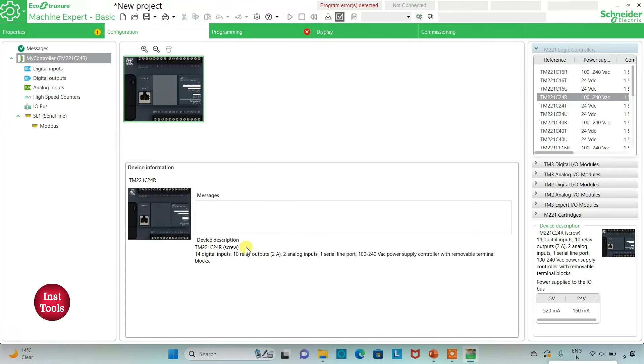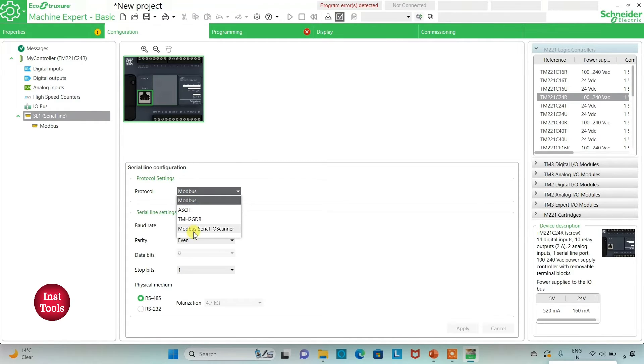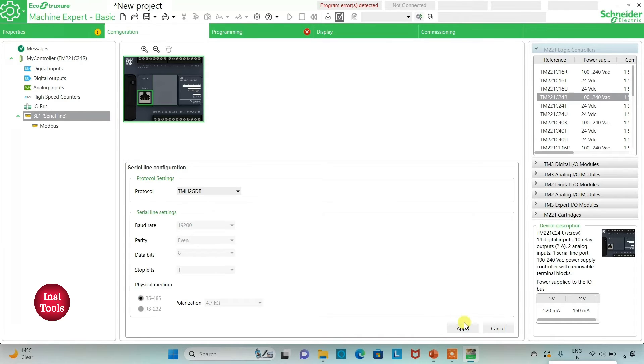Here is a device description about TM221C24R. It has 14 digital inputs, 10 relay outputs, 2 analog inputs, 1 serial line port, and 100 to 240 volt AC power supply controller with removable terminal blocks. After that, I can also go to Serial Line, where I will select the protocol as TMH2GDB. I can also set it as Modbus ASCII TMH2GDB or Modbus Serial IO Scanner. I will keep it TMH2GDB for now, and click Apply. If I keep protocol as TMH2GDB, there is no need to set the Serial Line settings.